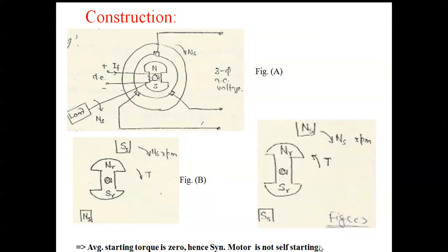This is a very important conclusion: the synchronous motor is not self-starting. If we apply three-phase supply and DC to the rotor, the motor will not run because the average starting torque is zero. This happens because of inertia — the rotor cannot instantly catch up with the rotating field.